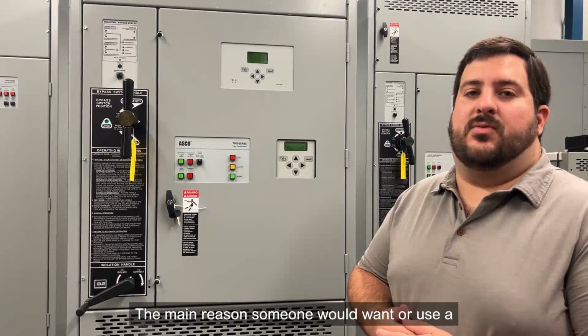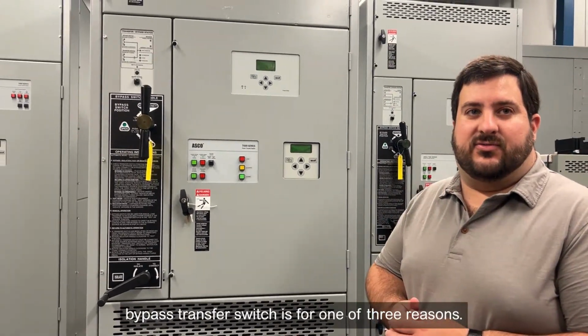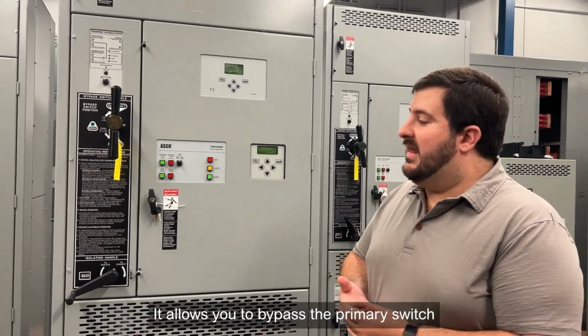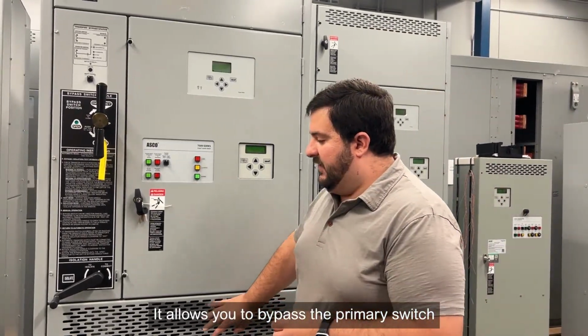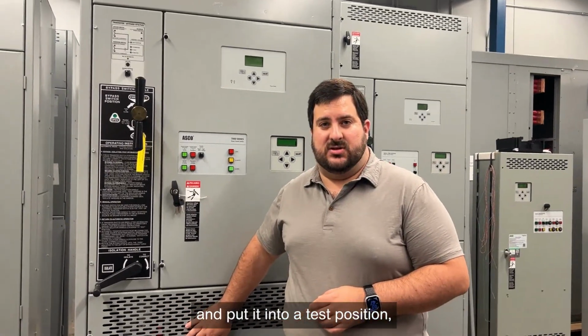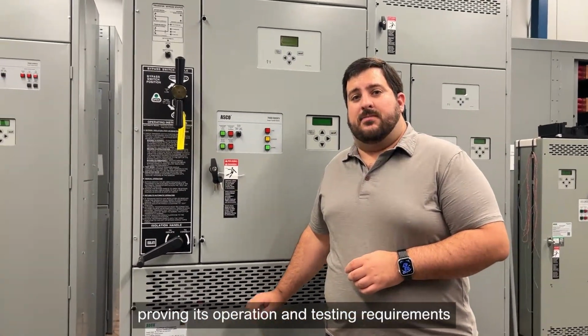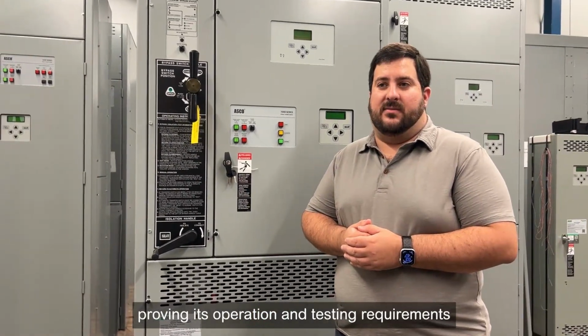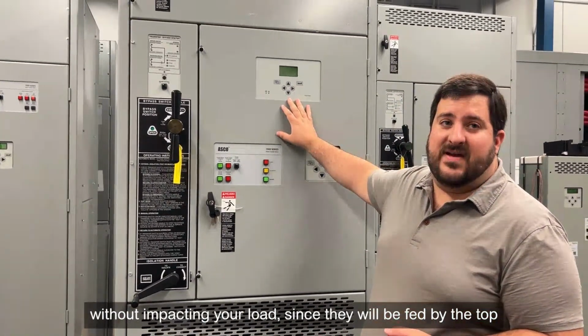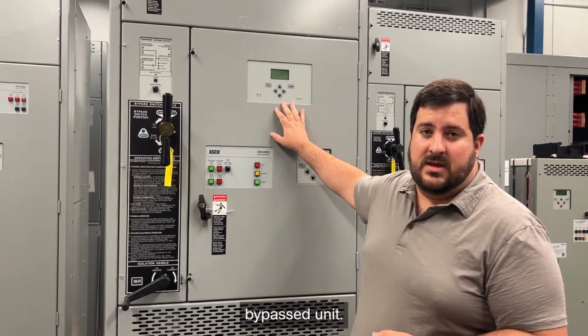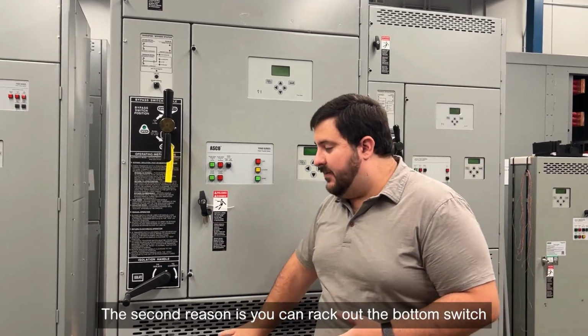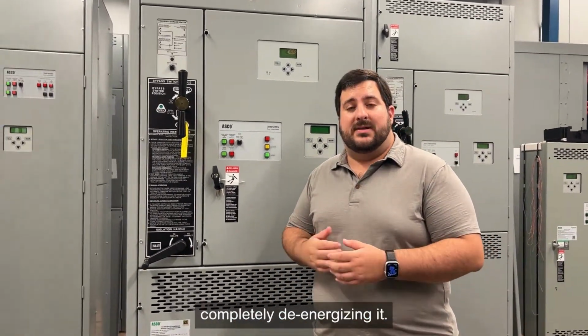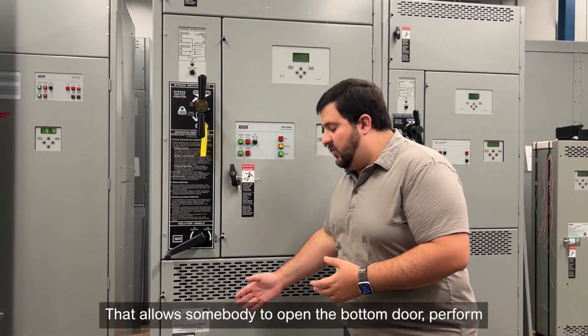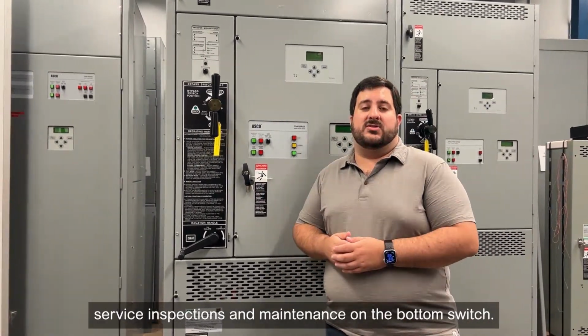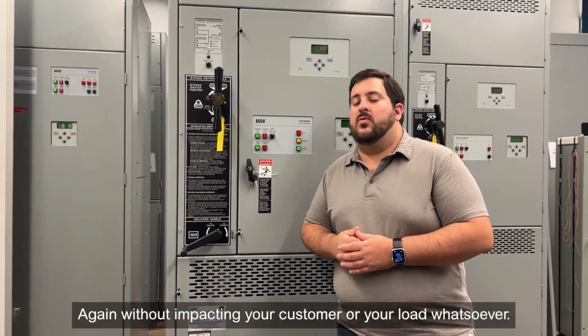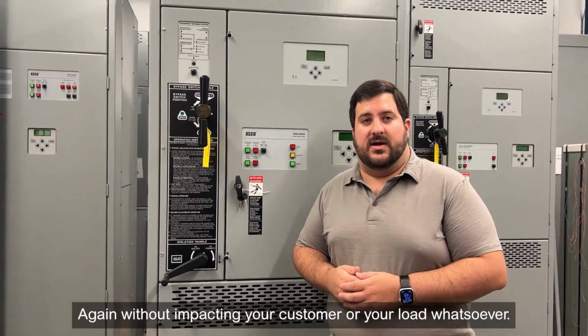The main reason someone would want or use a bypass transfer switch is for one of three reasons. It allows you to bypass the primary switch and put it into a test position, allowing you to operate the bottom switch, proving its operation and testing requirements without impacting your load, since they will be fed by the top bypassed unit. The second reason is you can rack out the bottom switch all the way out to an isolate position, completely de-energizing it. That allows somebody to open the bottom door, perform service, inspections, and maintenance on the bottom switch, again, without impacting your customer or your loads whatsoever.